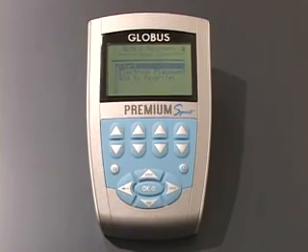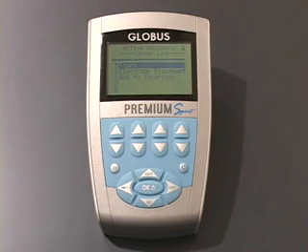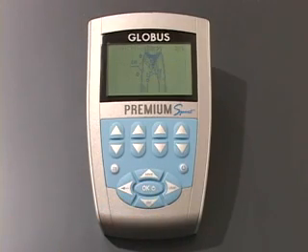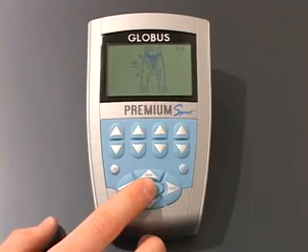We're ready to start the program. If you needed some guidance on pad placement, you can refer to the pad placement guide in the quick start manual. Or, right on screen, you can choose electrode placement and it will show you exactly where to put the electrodes.